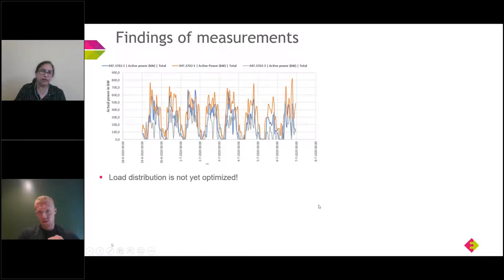As I mentioned, the site is not yet complete, so we are going to have more buses. As expected, the transformers are not fully loaded. As you can see in this graph, the maximum loading of each transformer is 600-700 kilowatt, while it can load up to, say, 1500 kilowatt. So it is approximately 40% loaded.